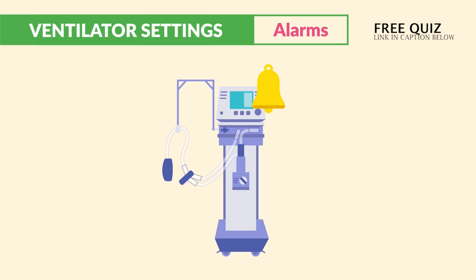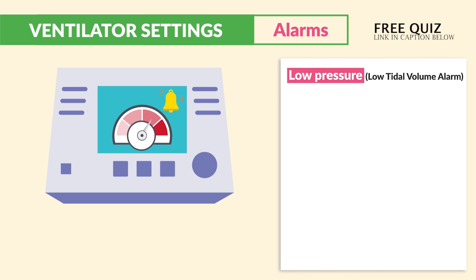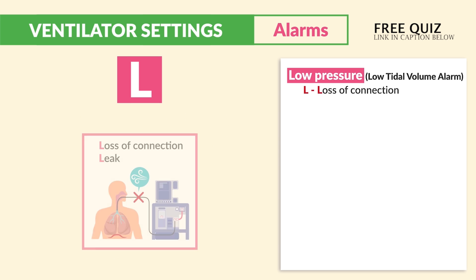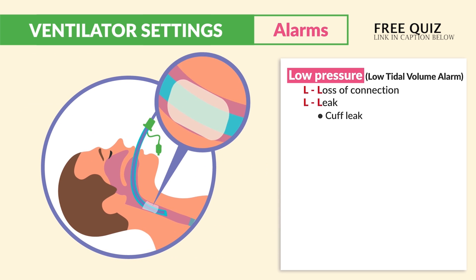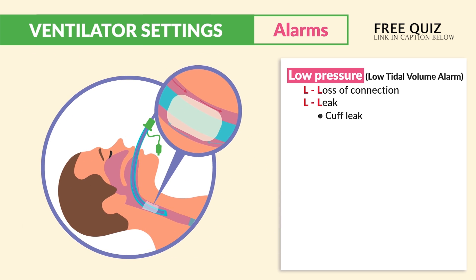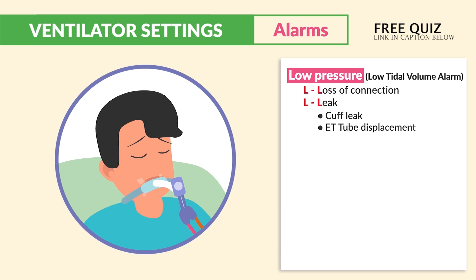We have two types of alarms: low pressure and high pressure. For low pressure, this is known as a low tidal volume alarm — just think of the double L's. It means we have a loss of connection resulting in an air leak, typically caused by a cuff leak that's not tight enough or ET tube displacement.